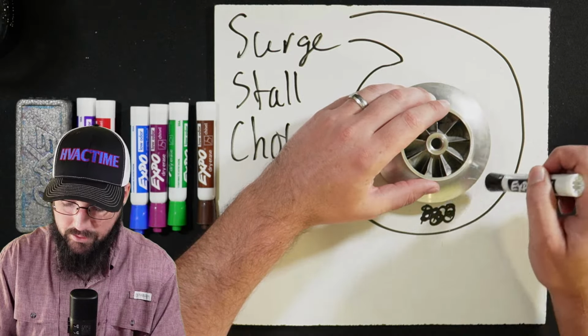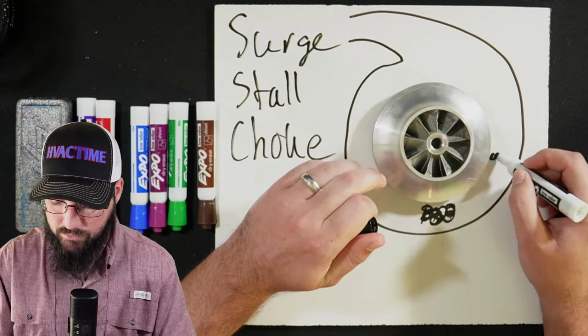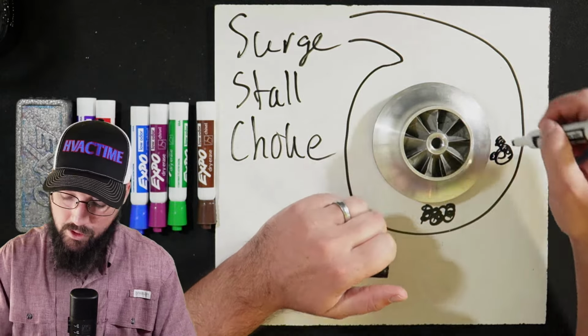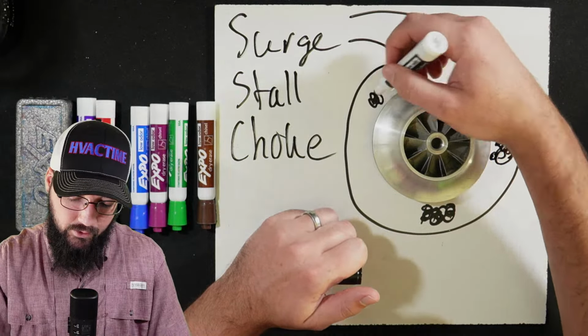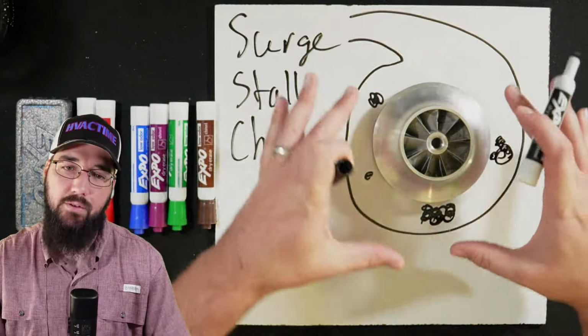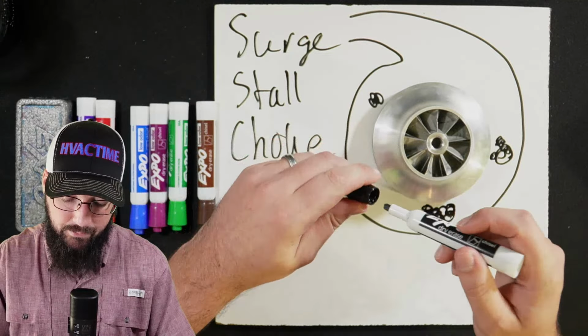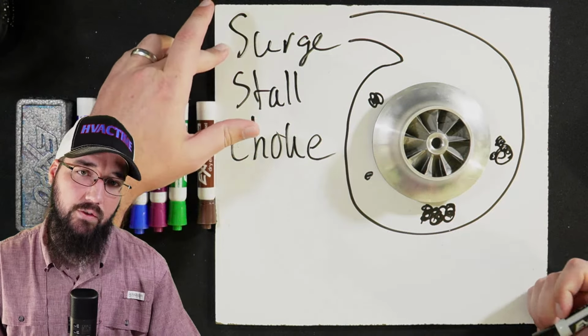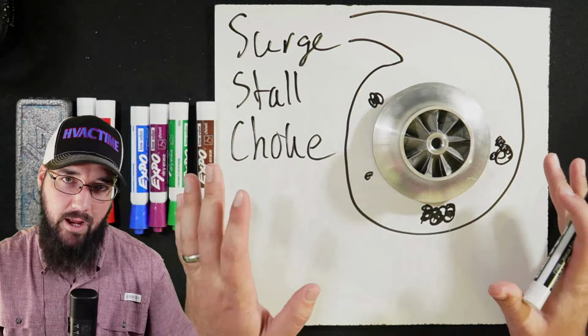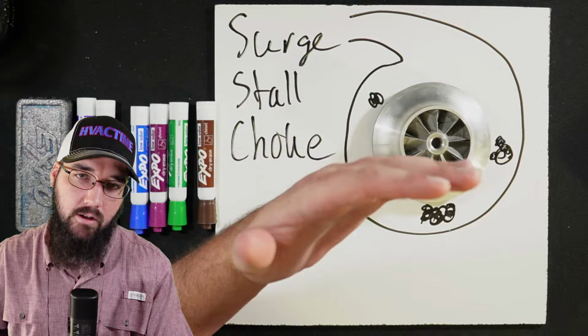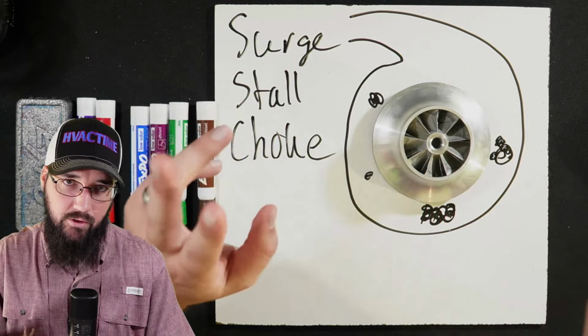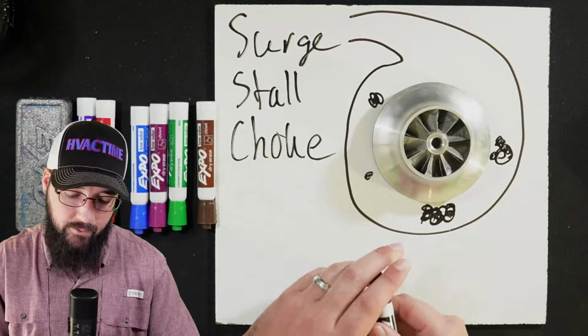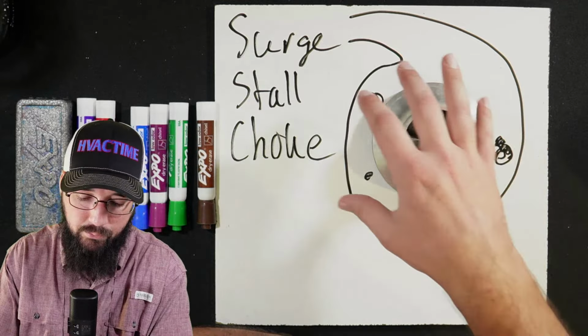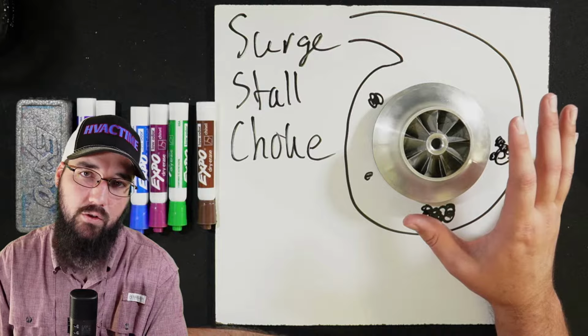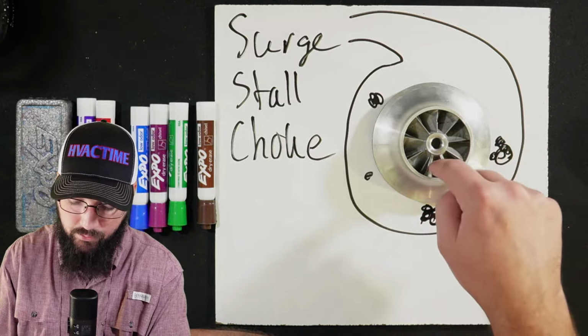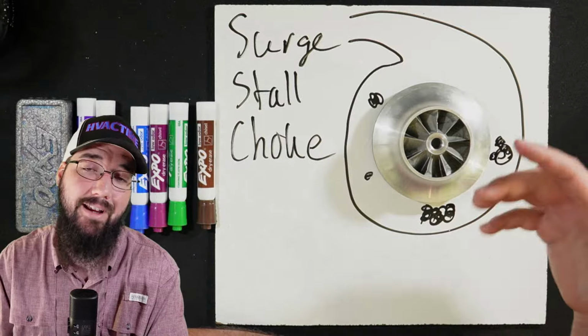And then the worse the stall gets, we have more eddy currents and more turbulence, and eventually enough of this builds up and instability forms and a surge happens next. So a stall precedes a surge. Now this can happen extremely rapidly, so we could go straight from normal to surge real fast, and there's technically a stall moment in between there. But we also have conditions where we're not actually surging, but we push up into a stall state where we have certain vanes that are not moving, and that creates imbalance.